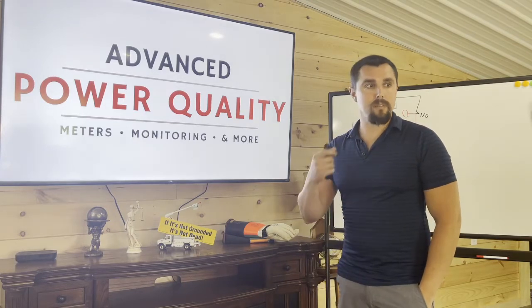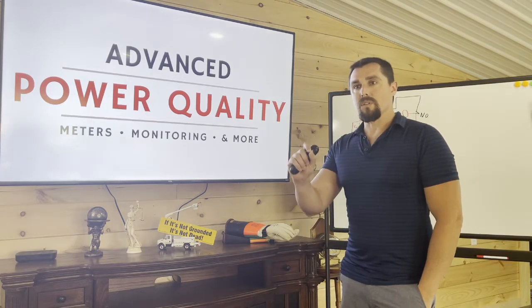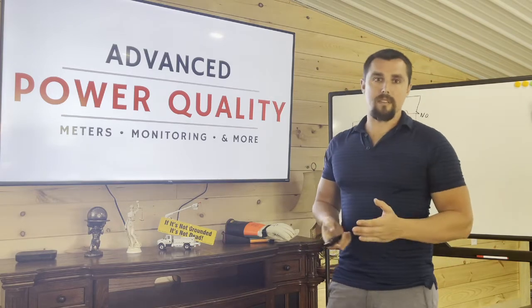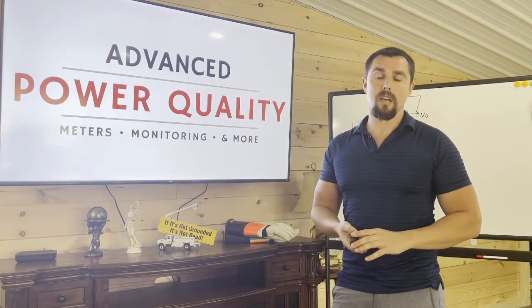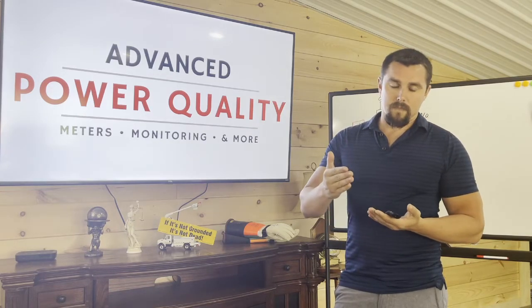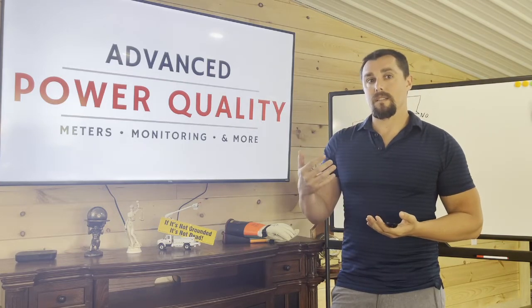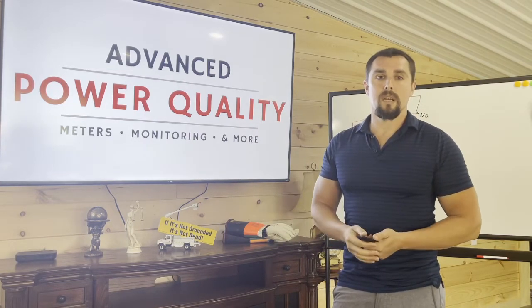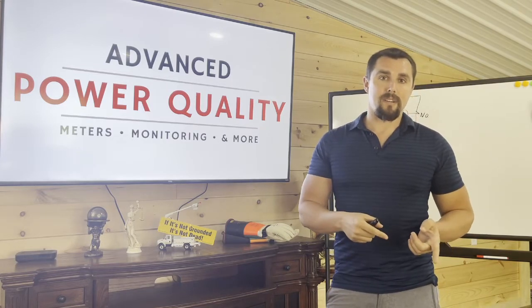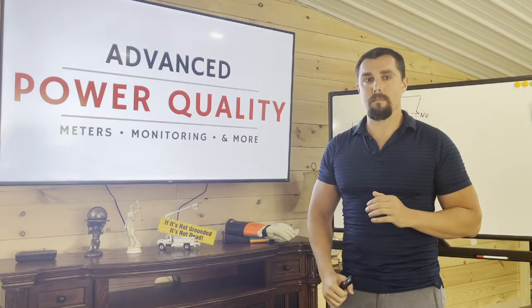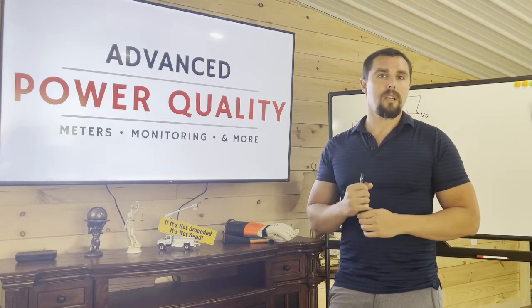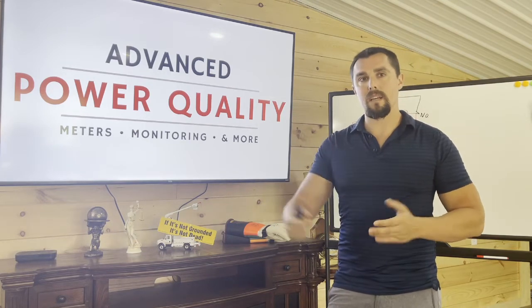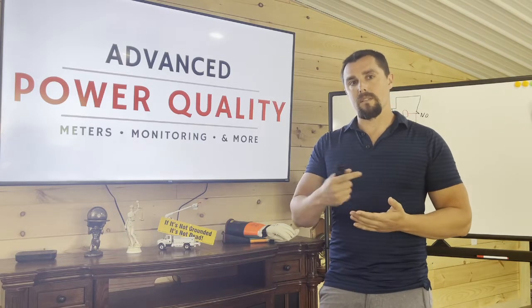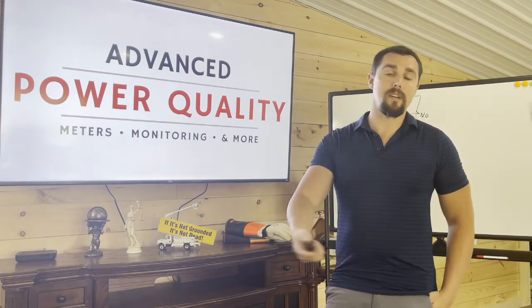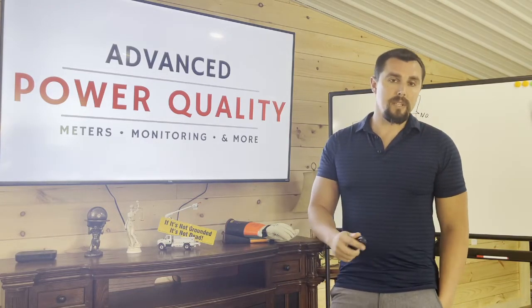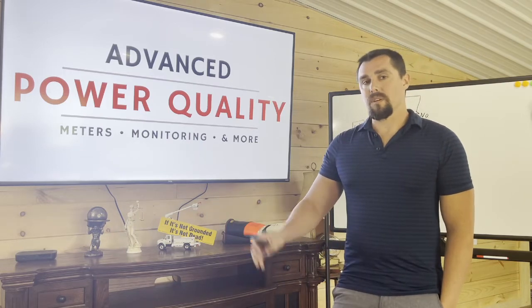I was actually working with a utility about a year ago where they overlooked their protection scheme, and what breakers have is a fault current recognition. It's a minimum current. So what happens is current reaches that value and the breaker recognizes it as fault current. Well, their load on that breaker reached that level, and the breaker operated, I want to say, about 23 times in a 1 hour period. It has about a 2 minute restart if the breaker doesn't recount each time, so it never went into lockout. The customers on that feeder saw 23 operations. Now that's torture on any equipment.